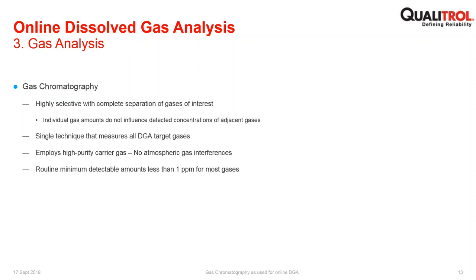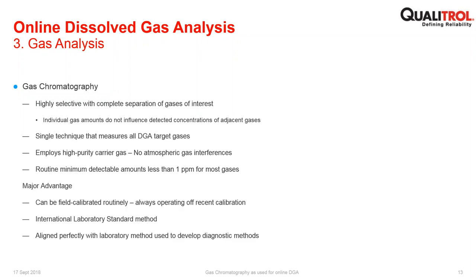And gas chromatography provides routine minimum detection limits of about 1 ppm for most gases. This is not uncommon for a lot of the techniques. But 1 ppm is applicable for dissolved gas analysis, right? We usually need detection in the tens to hundreds of ppm for diagnostic purposes, but most of the standards will call out 1 ppm as a lower detection level.